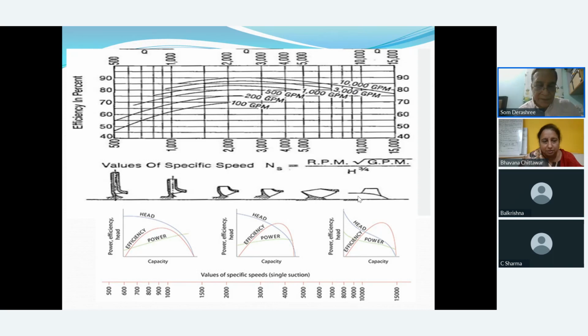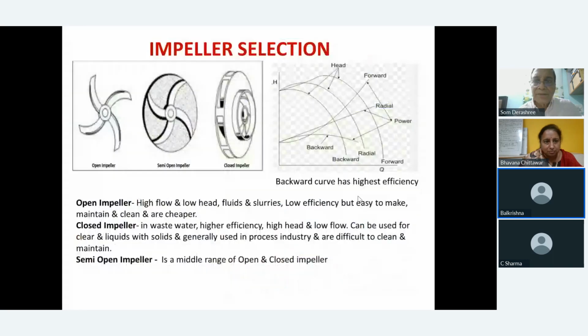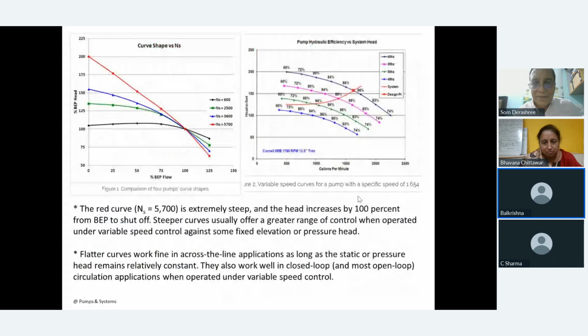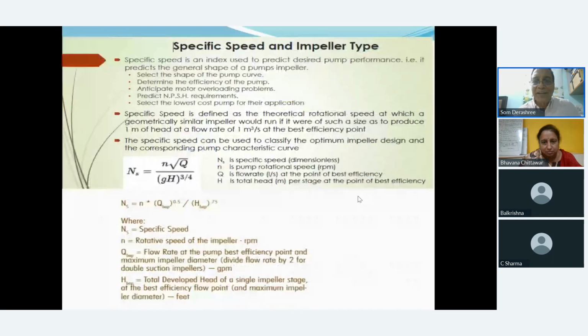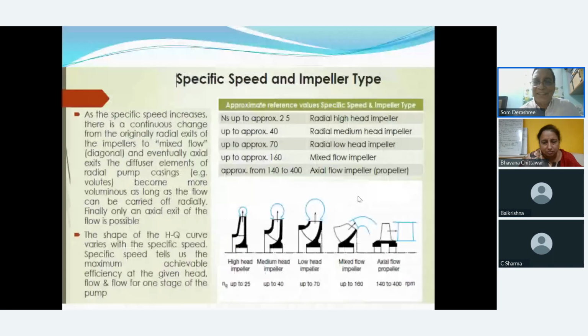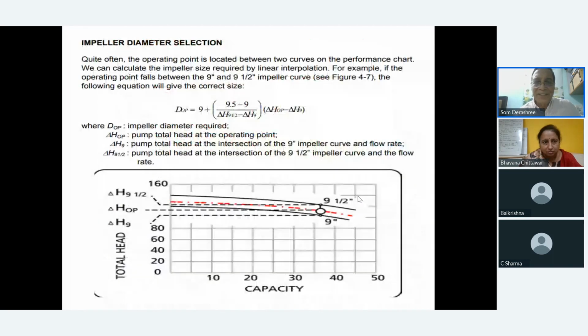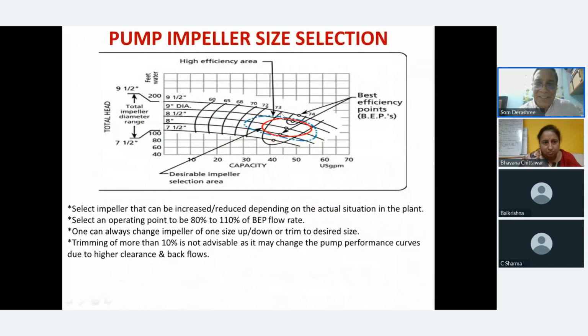Hello. Yes, sir. My previous question was regarding where the design point is selected. Books say that it should be on the right-hand side of the best efficiency point, because with the deterioration over time, the point would align towards the best efficiency. So I was asking that question. Okay. So either side. I mean, you see the efficiency curves. The 73 curve is like this. Now, what is left, what is right, I don't know. What do you mean by this? But if you select on the left-hand side, sir, what will happen over a period of time when the system head increases because of the deterioration in the pipeline, the efficiency would drop further.